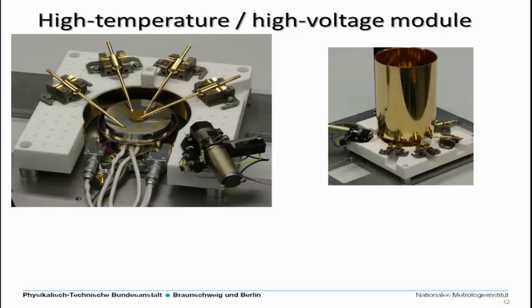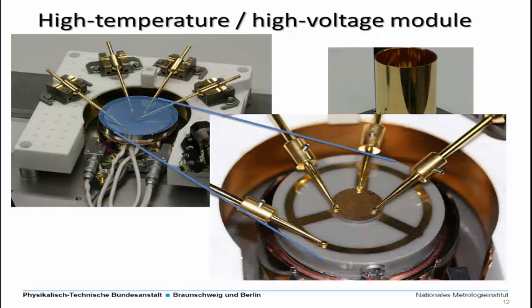This is the sample holder here on the left, in the left picture. In the center you see a heating module, and on the top of this heating module you have the reference plate and the sample under test, which can be contacted for the application of the electric field via these gold-coated levers. And on the top of the reference plate you also see this gold pattern for the contact to the lower electrode of the sample. Then we add this gold-coated shield in order to protect the surrounding optics inside the vacuum chamber from the heat radiation. And if we take a closer look to the center of the setup, you see also here this small hole inside the reference plate.